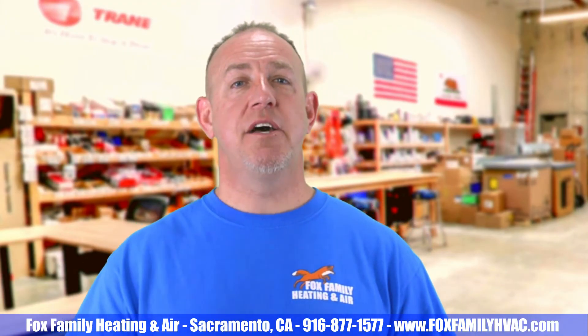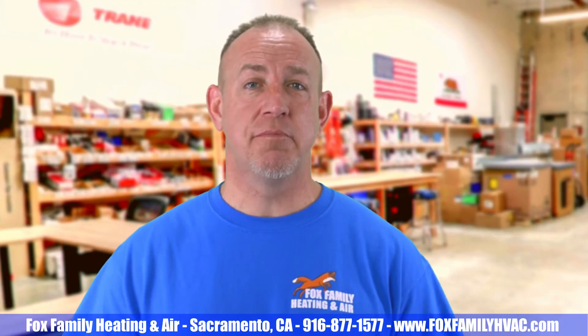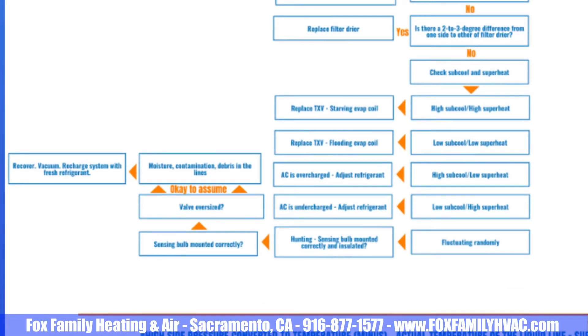So what can we tell using superheat and subcooling? First, figure out what your superheat and subcooling are supposed to be that day. A high subcool and high superheat tells you that the TXV is restricted and starving the evaporator coil. Low subcool and low superheat tells you that the TXV is overfeeding or flooding the evap coil. Low subcool and high superheat tells you that the system is just low on charge. While high subcool and low superheat tells you that the system is overcharged.